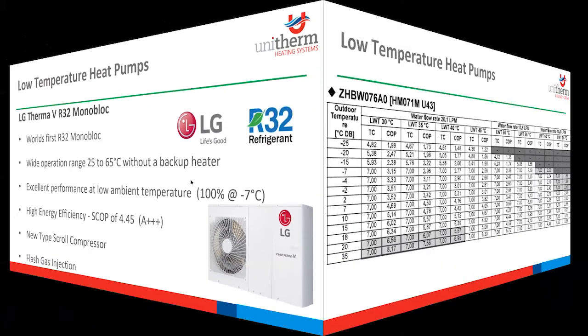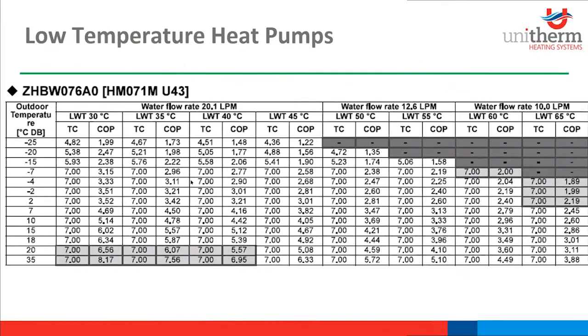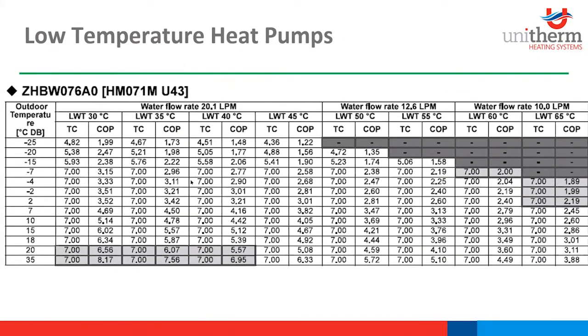Just going to have a quick look here at the capacity tables for a 7 kilowatt LG Therma V monoblock. So we'll just highlight the test standard there: EN 14825, air at 7, water 35. That's what all our heat pumps are tested at here. As we can see there, we have 100% performance down to -7. At -7, you're getting 7 kilowatts, with the COP at 2.96, all the way up from 35 degrees down to -7. And this total capacity of 7 kilowatts without a backup heater holds even up to 60 degrees leaving water temperature. So great for retrofits, great for any application with the wide operation range.